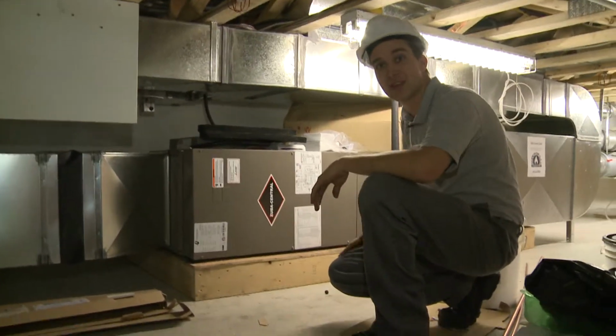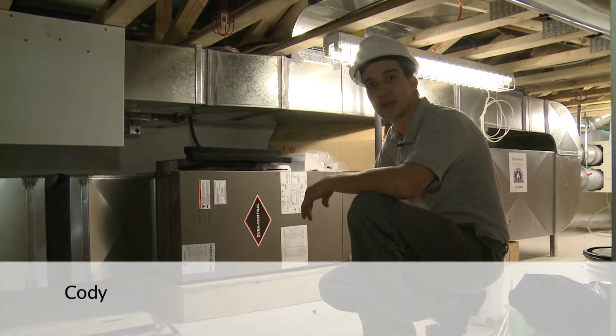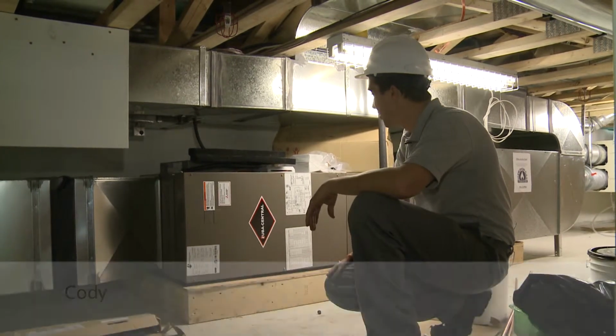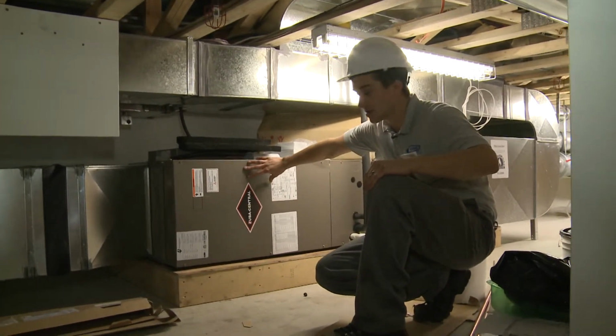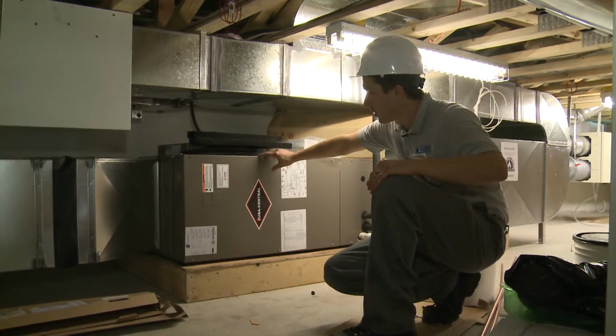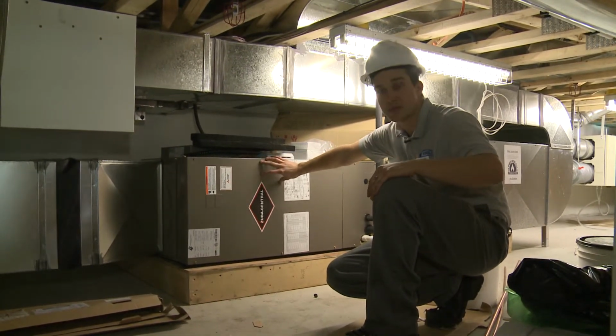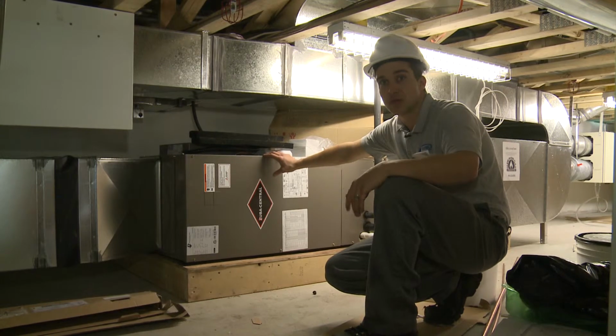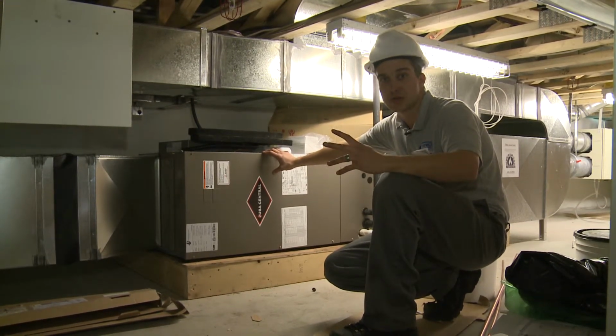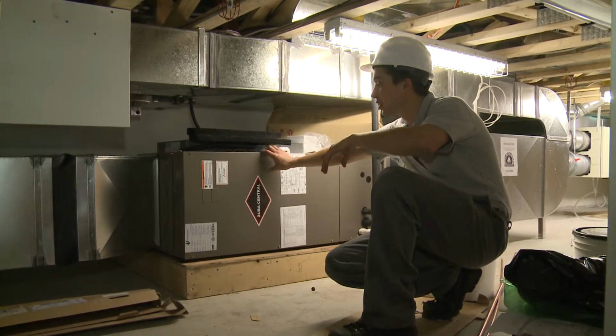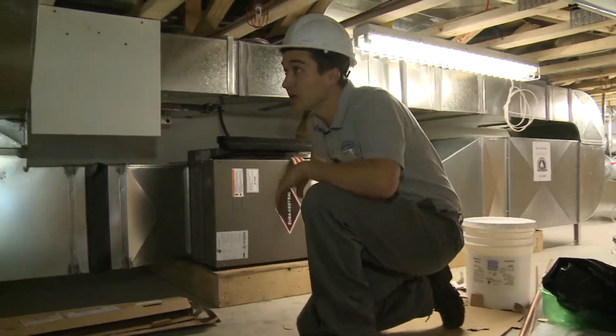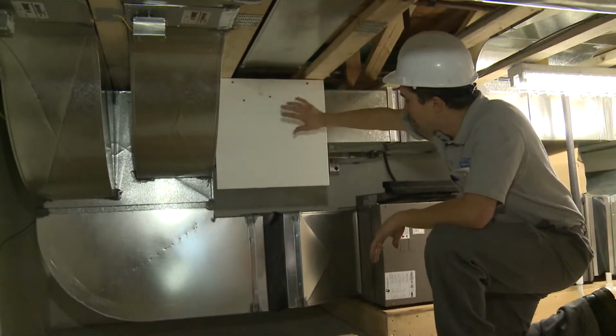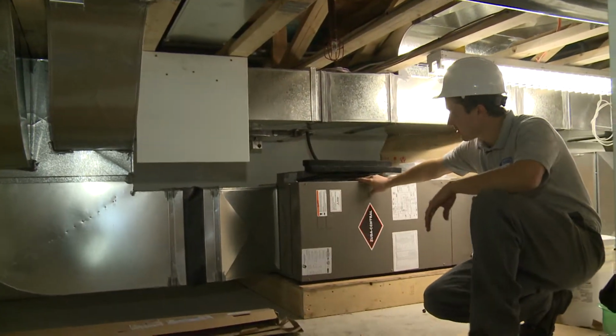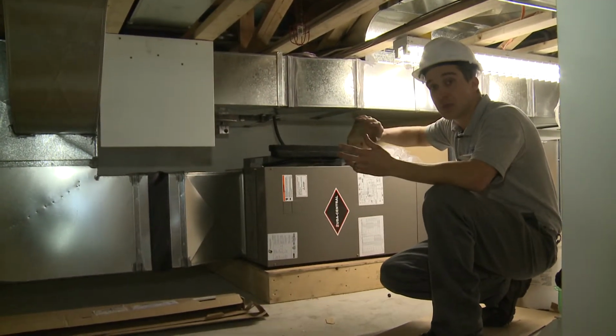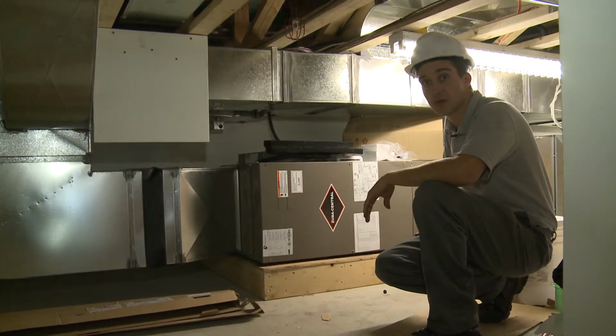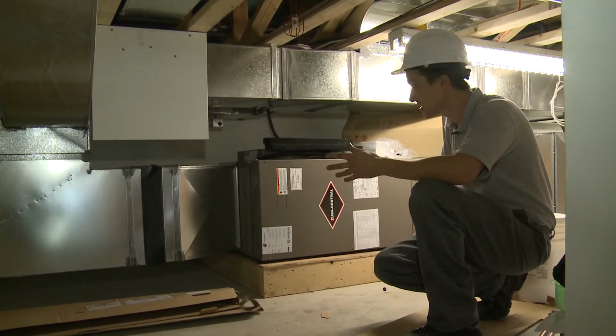Okay, I'm Cody. I'm working for Stoltz Mechanical, doing all the HVAC here. The main thing that heats and cools the whole house is this air handler here by Mitsubishi. It's 100% variable speed because in this building we got 2 different heat and cooling loads. And so there's a variable volume system with the zone dampers you see here. So those will be wired into a panel. And so there's a controller that will decide which space needs heat or which space needs cooling depending on the load and the thermostat, the zone sensor in the space.